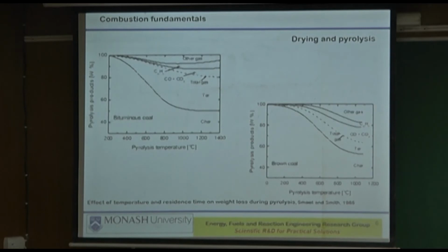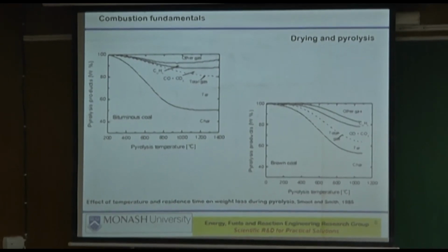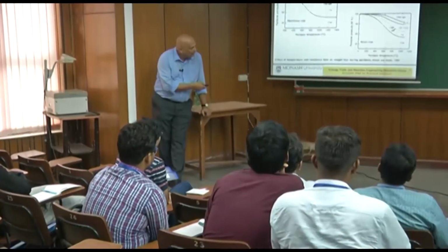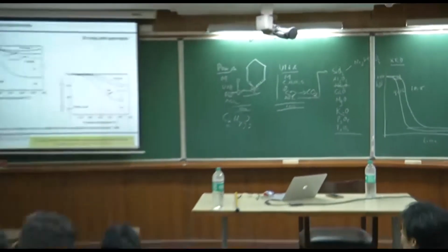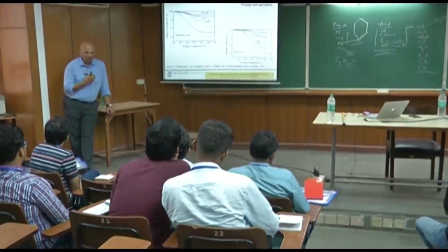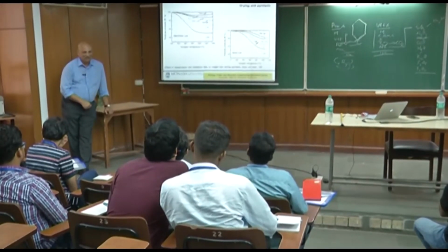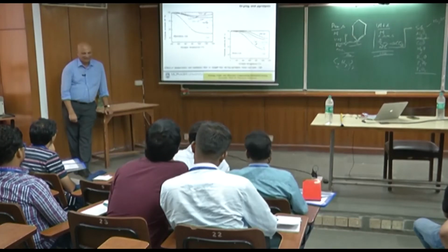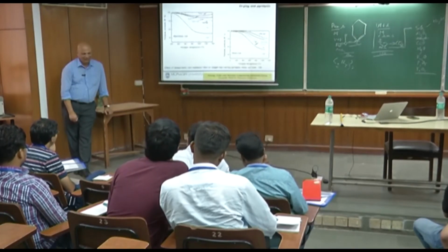So how much fixed carbon is present? That also depends on the temperature, because if you increase the temperature and keep on maintaining the temperature long and long and long, some of the fixed carbon will migrate to volatile matter and then will be released. So that's why it is extremely important for the designer to know the figures at a standard condition, which is 900°C for 7 minutes. And everything else can follow from there.